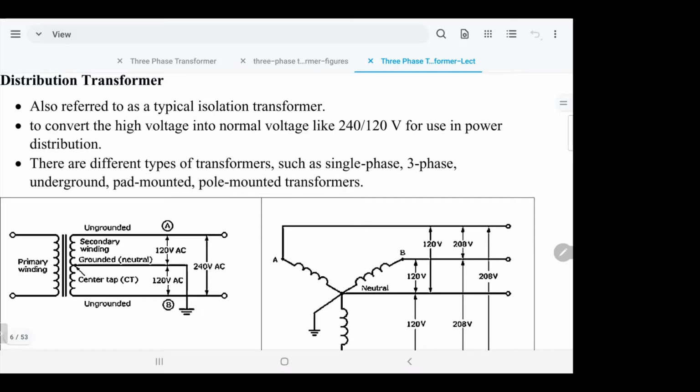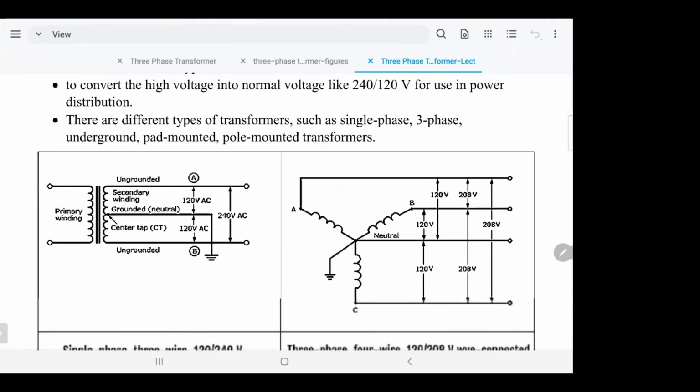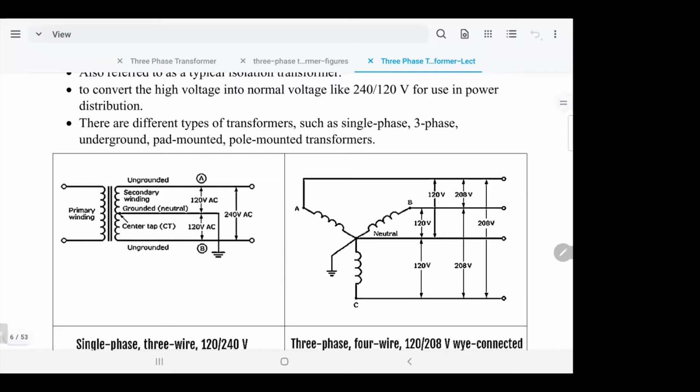All right. The power generation is in the main station. Usually there is a step-up three-phase transformer that steps the voltage from 380 volts up to 33 kilovolts. Then in the distribution system, it will go down. Actually, for distribution transformers, we have two types. They can use single phase and they can use three phase. Here is the three phase.